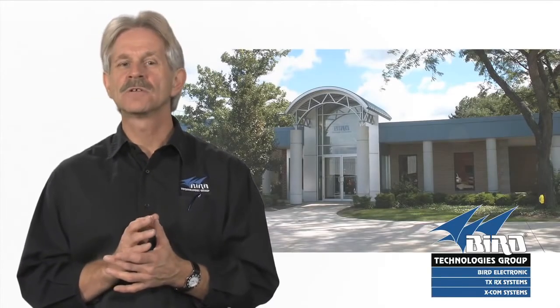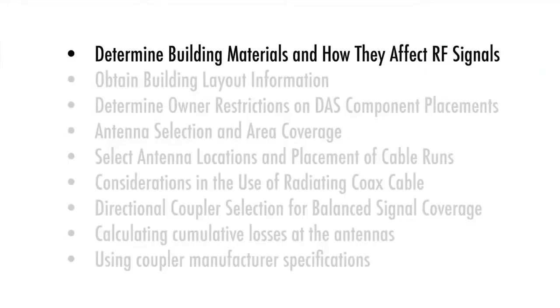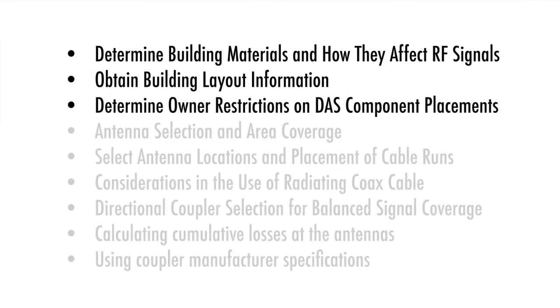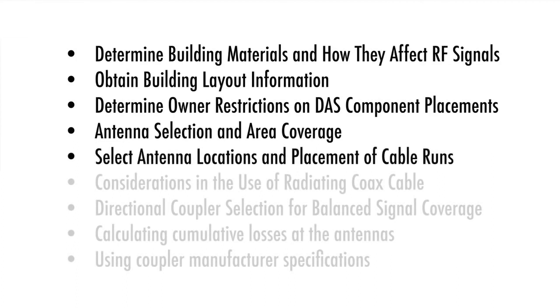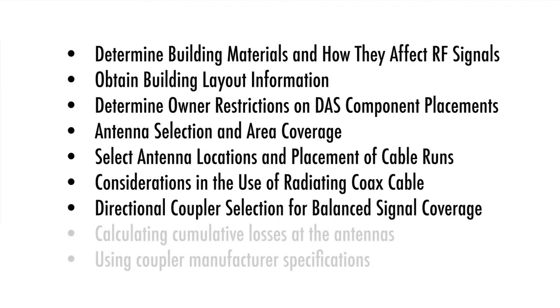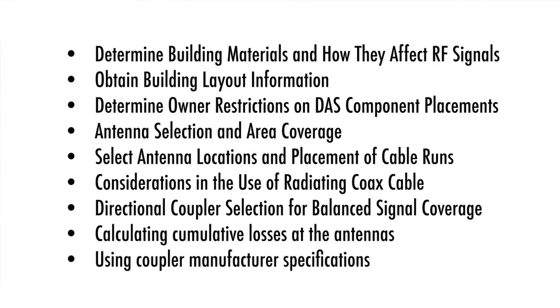Selecting the appropriate directional coupler is only one step in good DAS design. The other steps are: determine building materials and how they affect RF signals; obtain building layout information; determine owner restrictions on DAS component placements; antenna selection and area coverage; select antenna locations and placement of cable runs; consideration in the use of radiating coax cable; directional coupler selection for balanced signal coverage; calculating cumulative losses at the antennas; and using coupler manufacturer specifications.